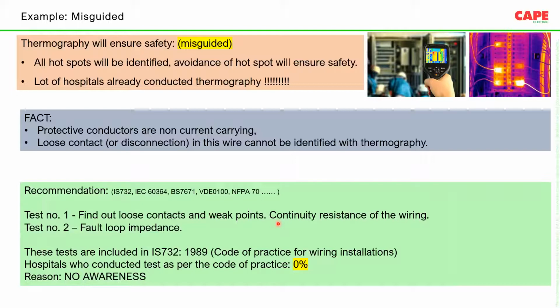Of course, it gives a certain amount of safety, but if you need 100 points for safety, how many points can you give for thermography? I would say maybe 0.5%. That's all, not more than that. That is the reason thermography is not recommended in IEC 60364. Thermography is recommended in low voltage only for solar PV, not for other applications, because the testing philosophy itself is different. I will explain it on the later slides.